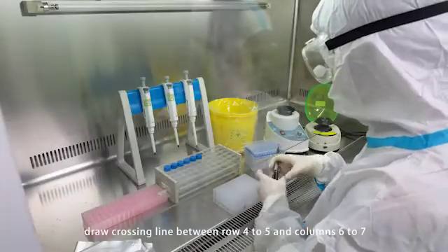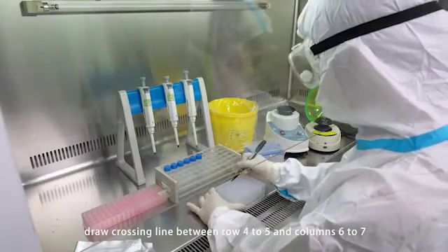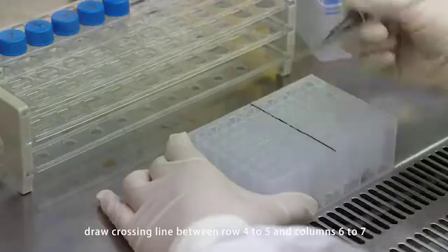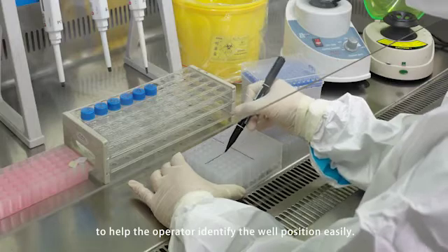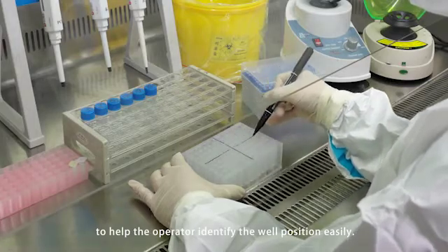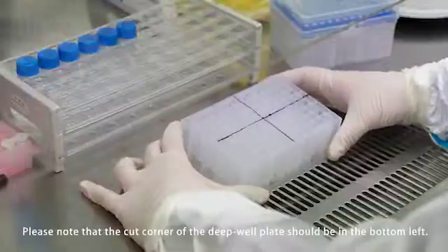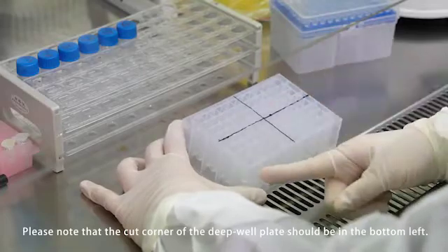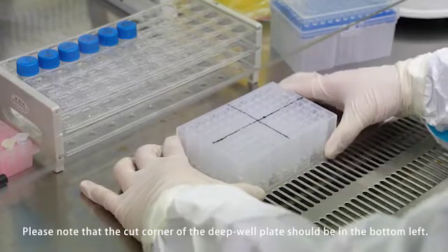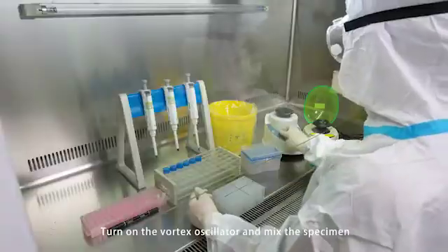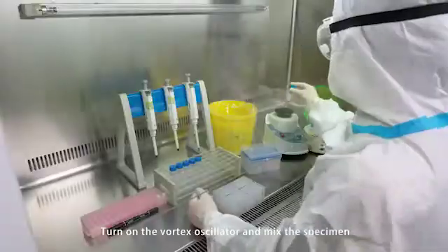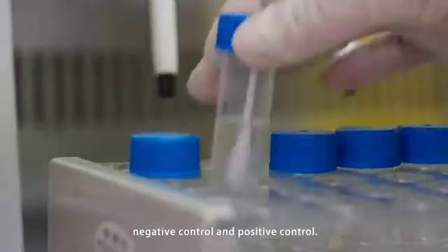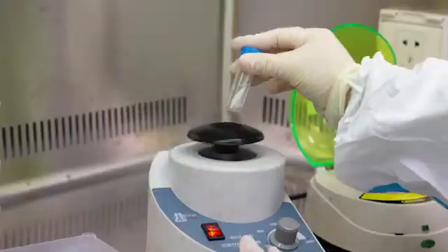Draw a crossing line between row 4 to 5 and column 6 to 7 to help the operator identify the well position easily. Please note that the cut corner of the deep well plate should be in the bottom left. Turn on the vortex oscillator and mix the specimen, negative control and positive control.